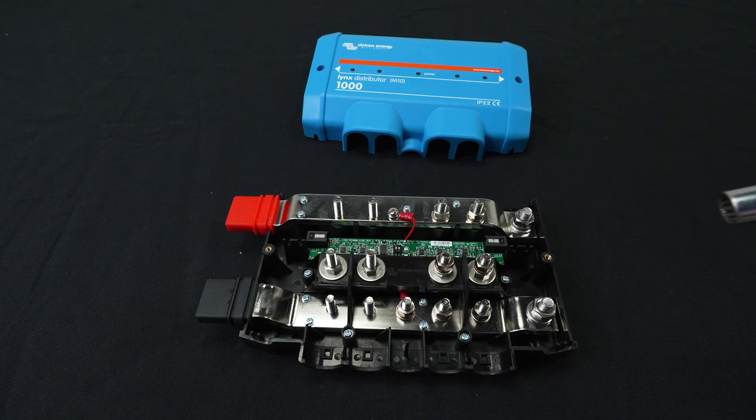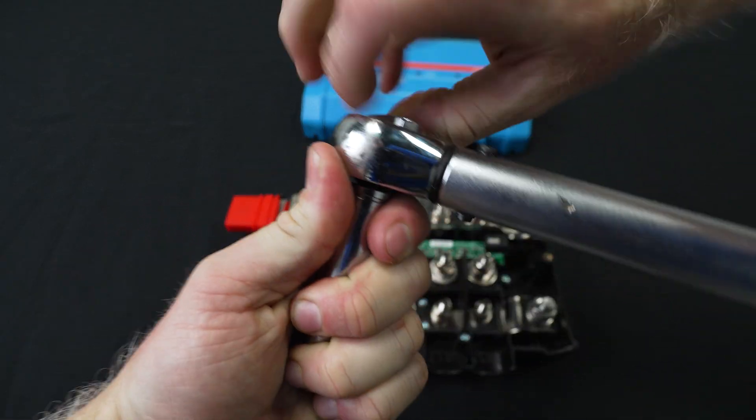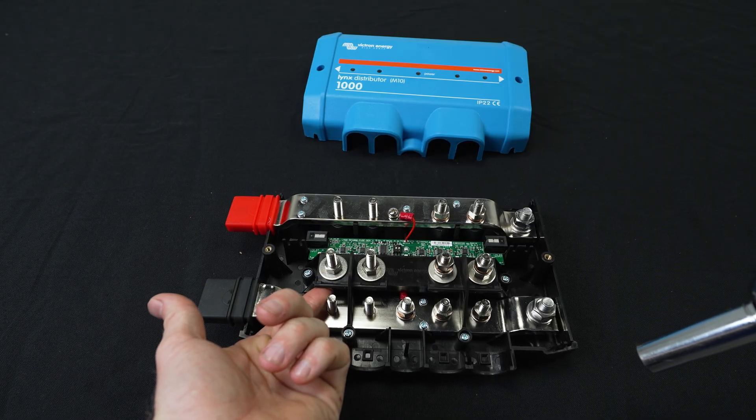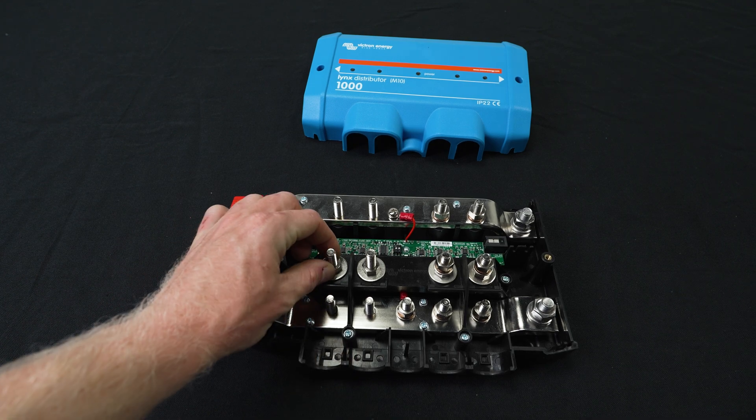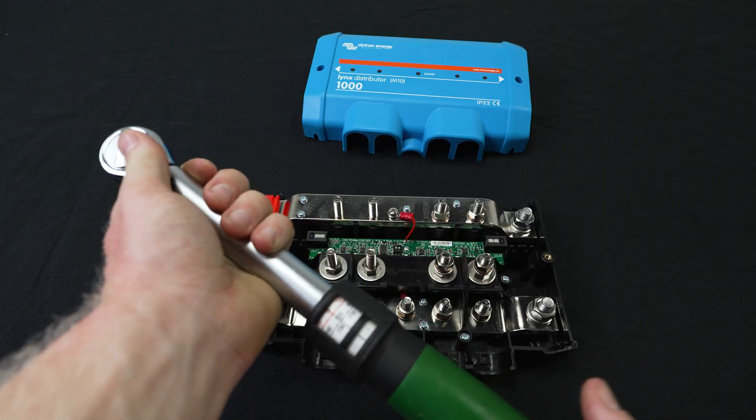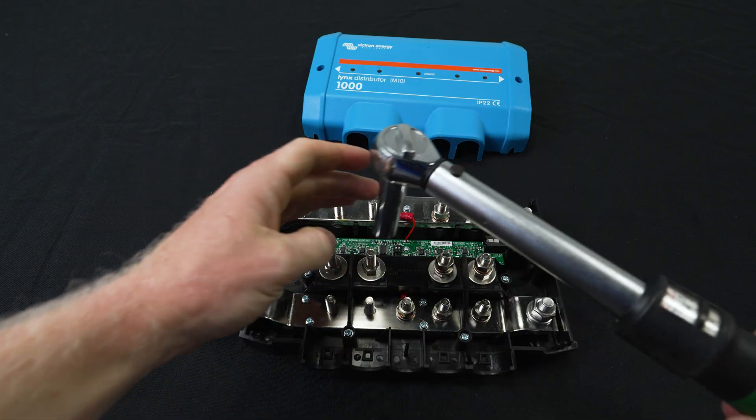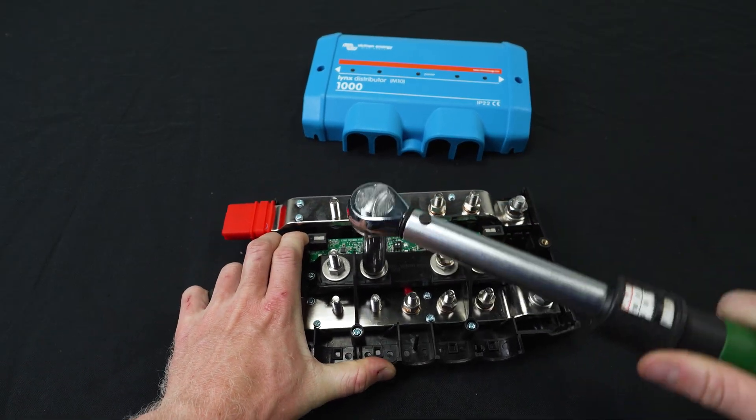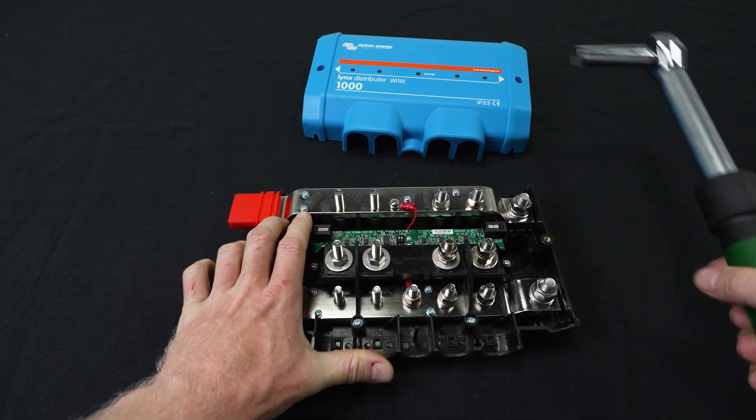So now the first step in preparing the Lynx distributor is to tighten the plastic nuts. There's a bolt under here we want to make sure that the head of the bolt is snug in the plastic and doesn't come loose. So we're going to set our torque wrench to 10 newton meters and just snug this up. You really don't want to over tighten these because it's just plastic holding the bolt in.